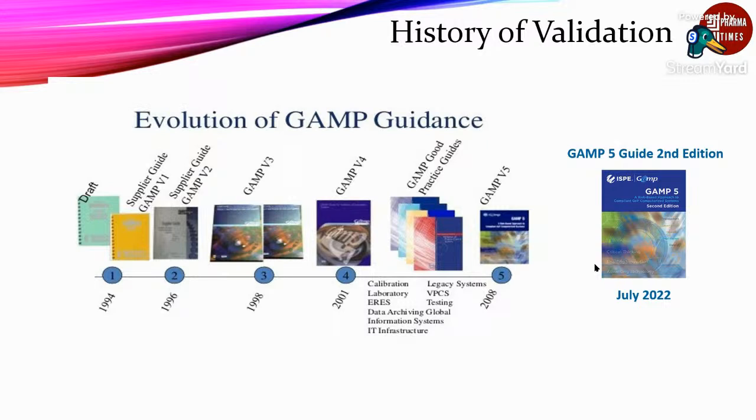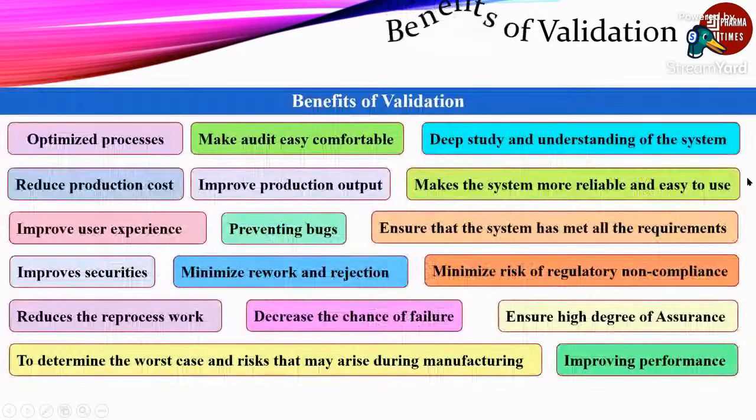And 21 CFR, we can say, is a regulation, so you must follow those rules. Generally, people get confused that it's a rule, that since it is written in GAMP 5 we must follow it. But GAMP 5 is already liberal for that. If you define the risk based on your process and your business perspective, then you can evaluate with your own system to comply with validation. So GAMP 5 is a guide, not a rule or any regulation that you must follow.